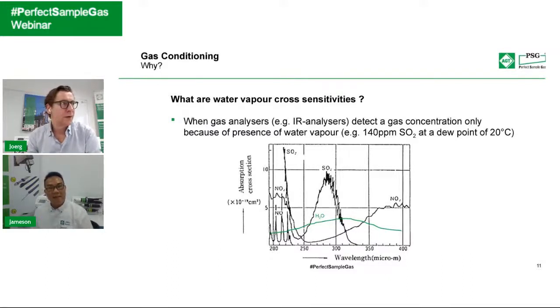The question is why gas cooler is set at 3 degrees. Why 3 degrees? Why not 4, why not 5? Because at 3 degrees it has been internationally recognized that the amount of water exceeding at the outlet of the exchanger is less than 1% water. It is negligible. To be exact, it is about 800 ppm.